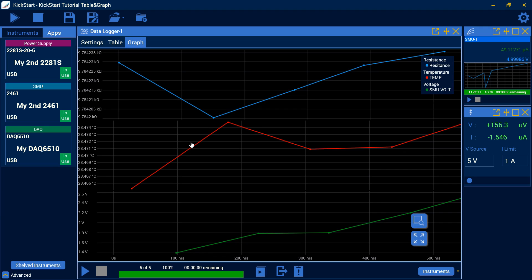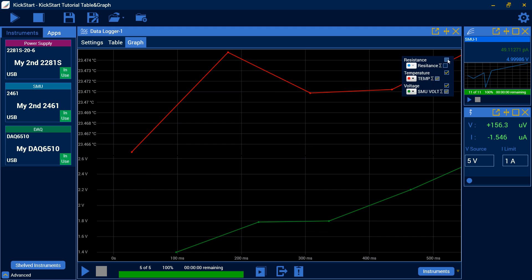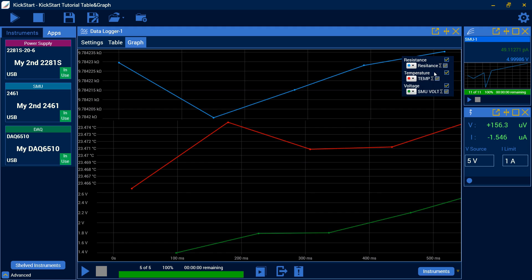Over on our graph tab, we can take a look. It's got all of our different values, and it shows in our table over here that resistance is our blue line. Temperature is the red, and our SMU voltage is the green. Although in here, we can change the color to whatever we'd like. We can disregard resistance or add it back in, and we can change all those functions around.